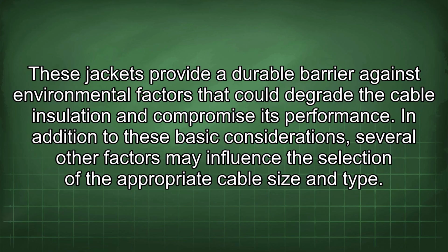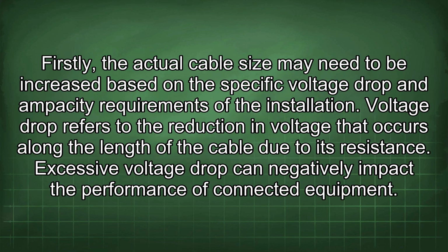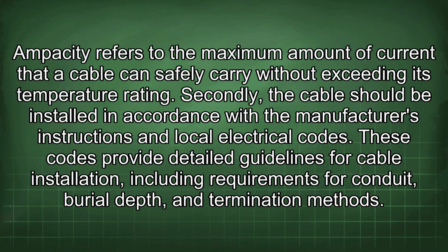In addition to these basic considerations, several other factors may influence the selection of the appropriate cable size and type. Firstly, the actual cable size may need to be increased based on the specific voltage drop and ampacity requirements of the installation. Voltage drop refers to the reduction in voltage that occurs along the length of the cable due to its resistance. Excessive voltage drop can negatively impact the performance of connected equipment. Ampacity refers to the maximum amount of current that a cable can safely carry without exceeding its temperature rating.